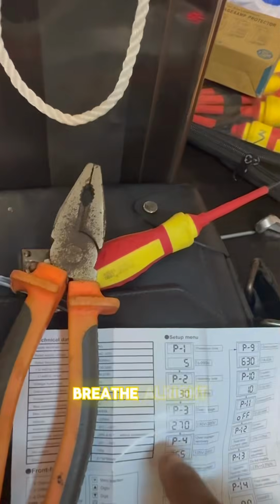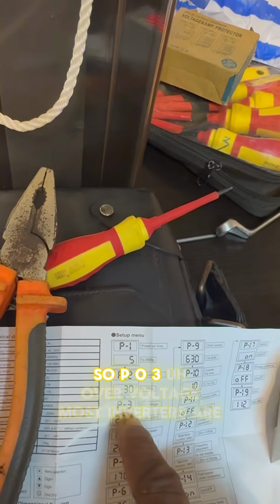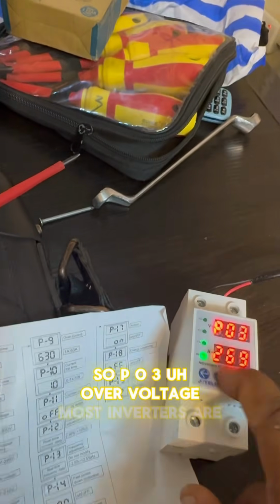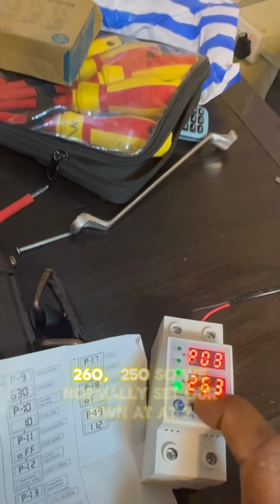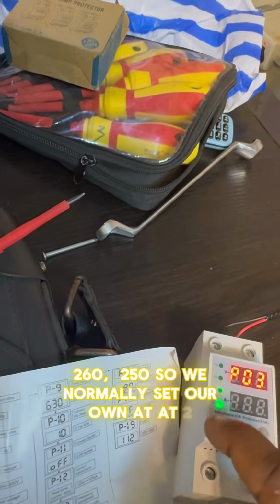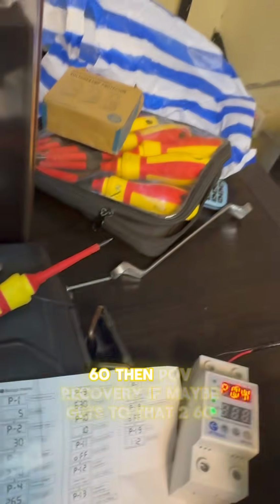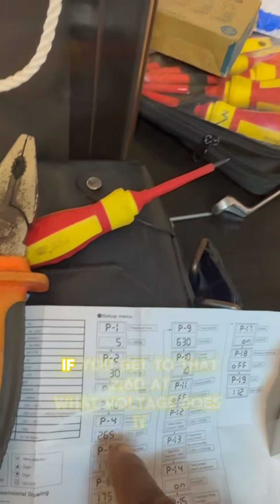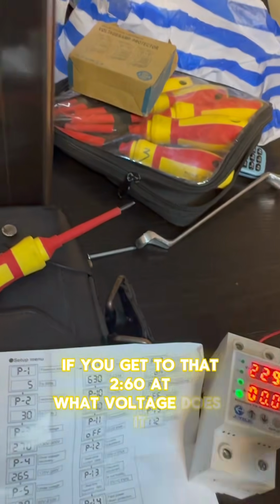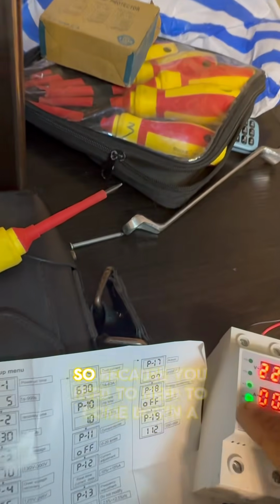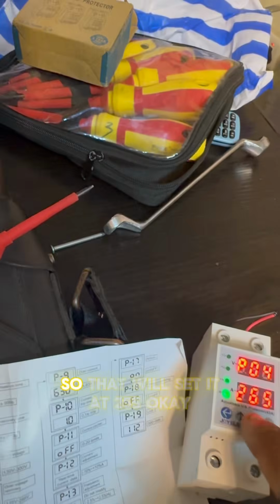All right. So PO3 over voltage. Most inverters are 260, 250. So we normally set our own at 260. Then POV recovery. If it gets to that 260, at what voltage does it reconnect back? Because it needs to come down a little bit, we set it at 255.